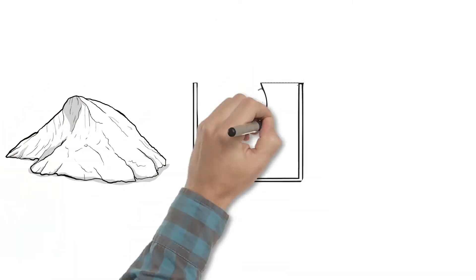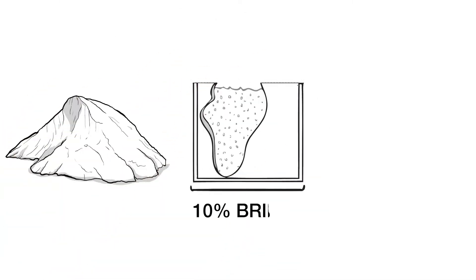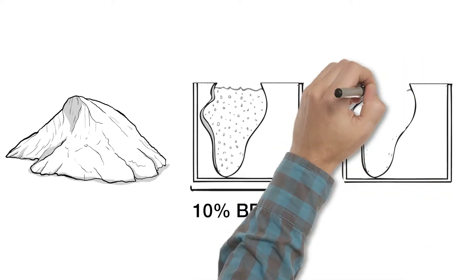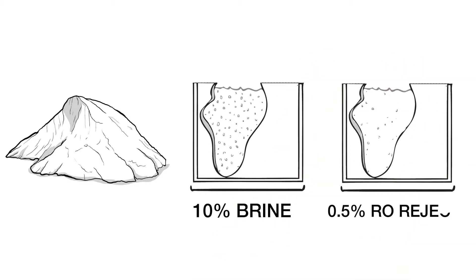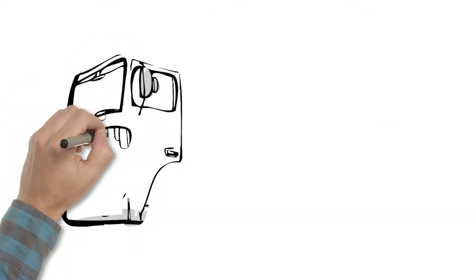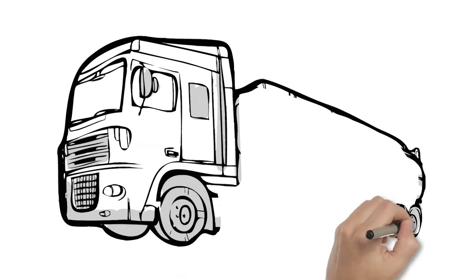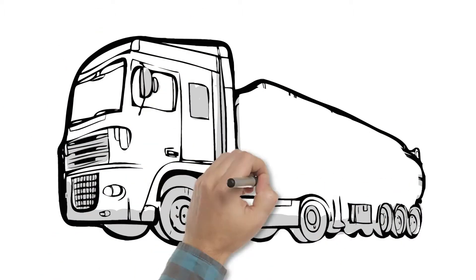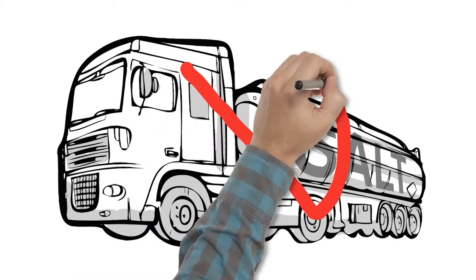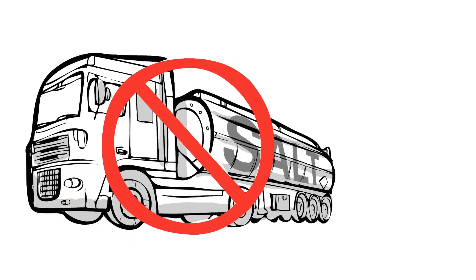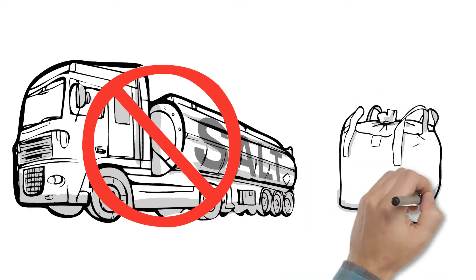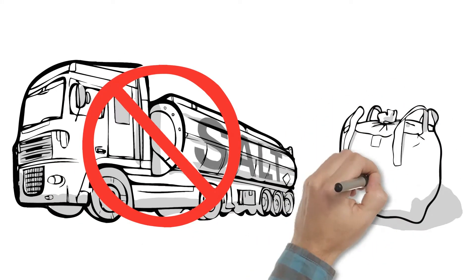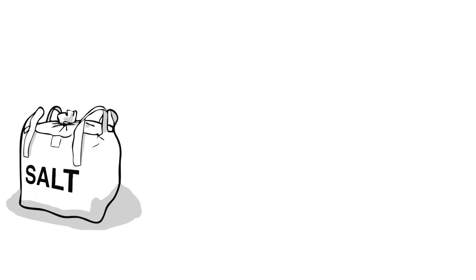With Purolite SST resin, the standard 10% TDS brine used for softener regeneration can be replaced with 0.5% TDS brine content of the RO reject water. This trademarked process is called Cyclic Ion Exchange Reverse Osmosis, or CIXRO. This means a 90% or better reduction in the purchased salt required for regeneration.